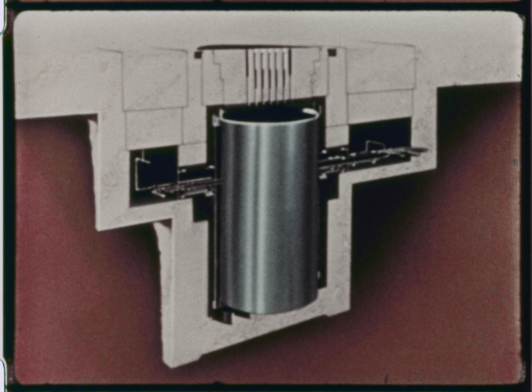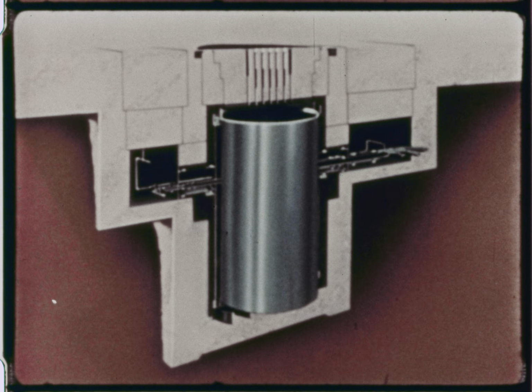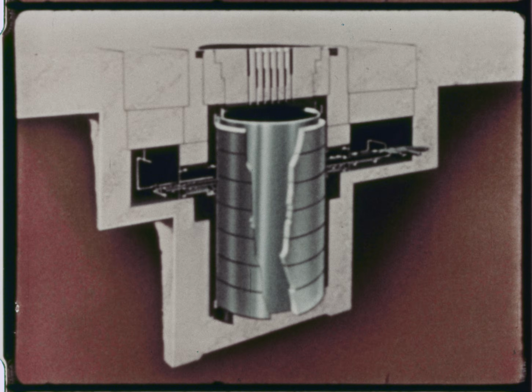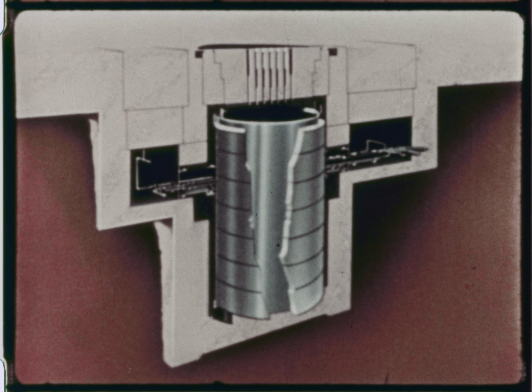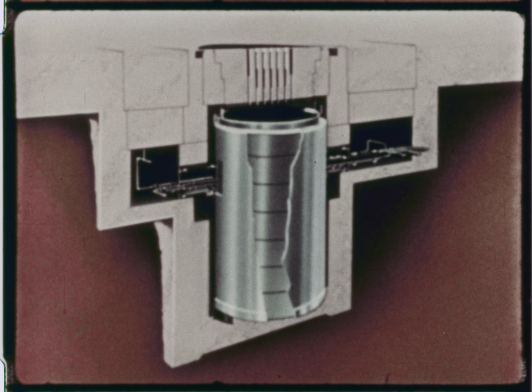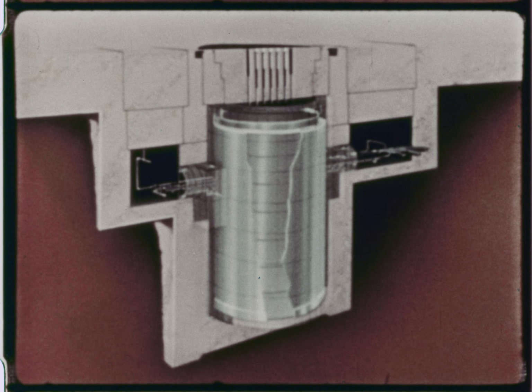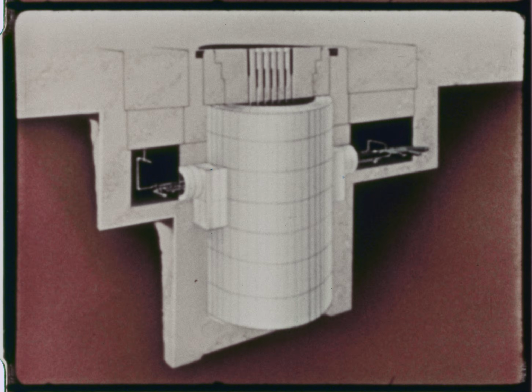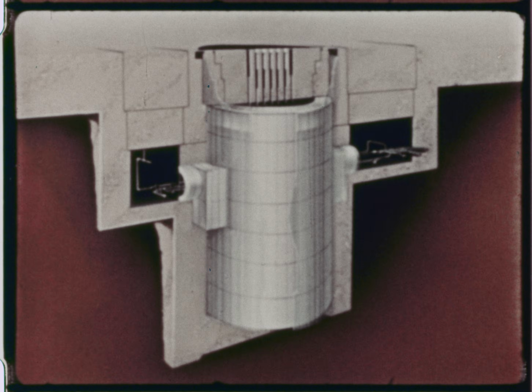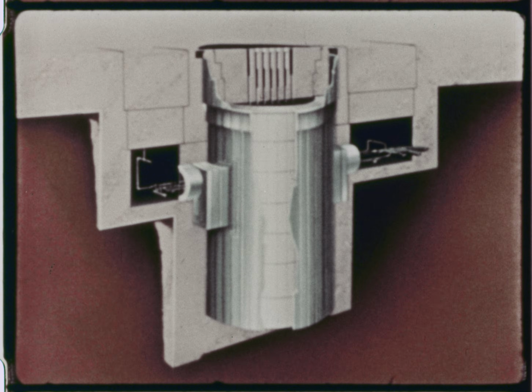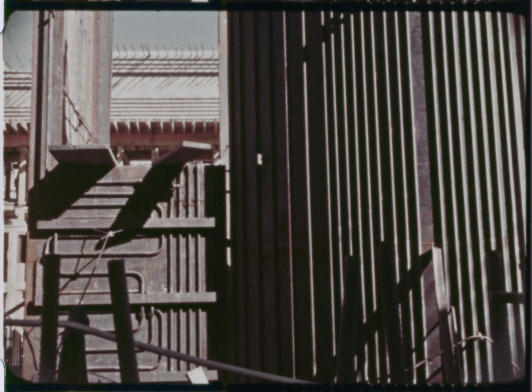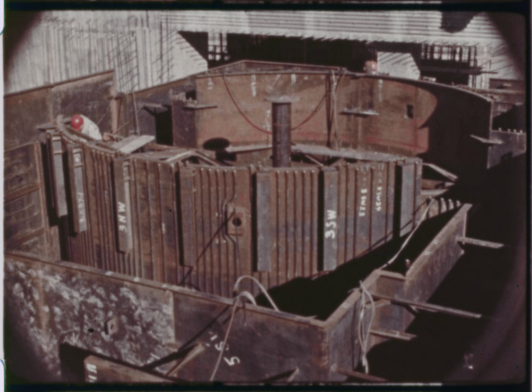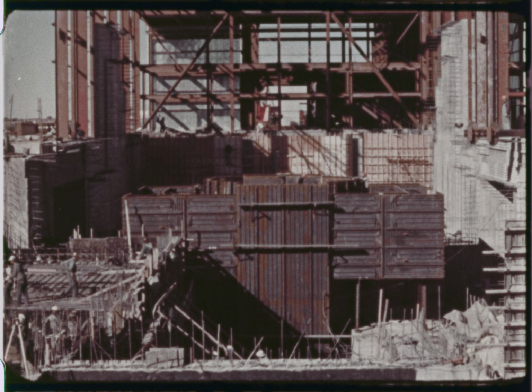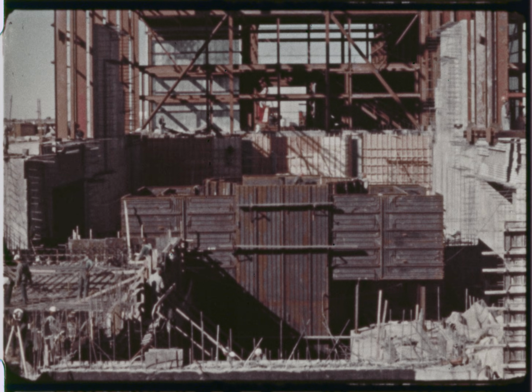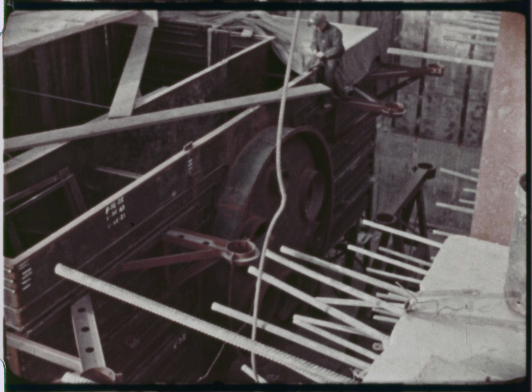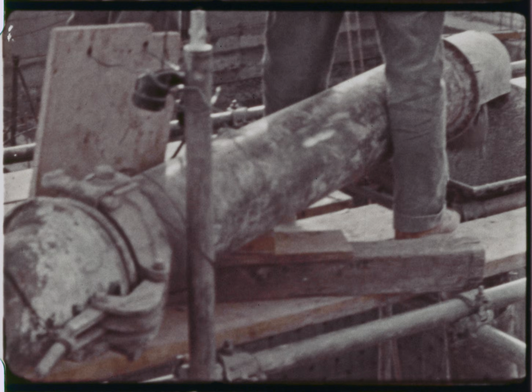The stainless steel reactor core tank, 19 feet in diameter by 33 feet in depth, is surrounded by a thermal shield, an outer tank, a layer of thermal insulation, and the reactor cavity liner, which is made of half-inch carbon steel. Steel pipe welded to the outer surface of the reactor cavity liner provides a means of circulating demineralized water to remove heat from the surrounding concrete. A pipe gallery accommodates sodium inlets and outlets to the core tank.